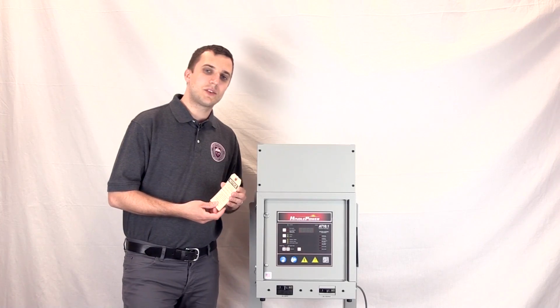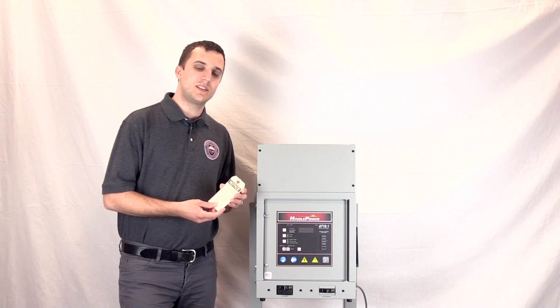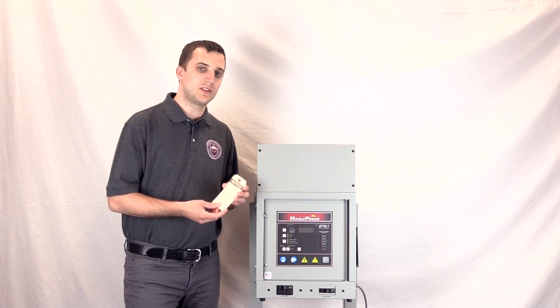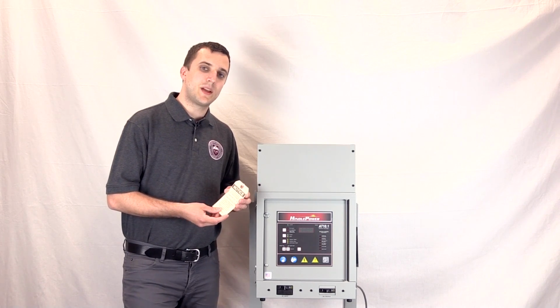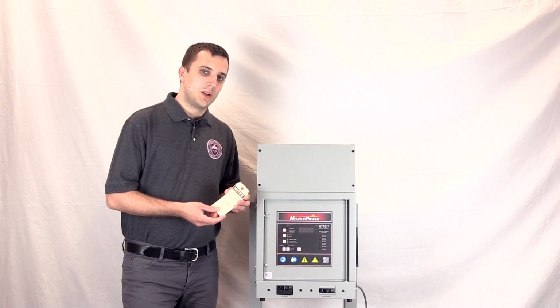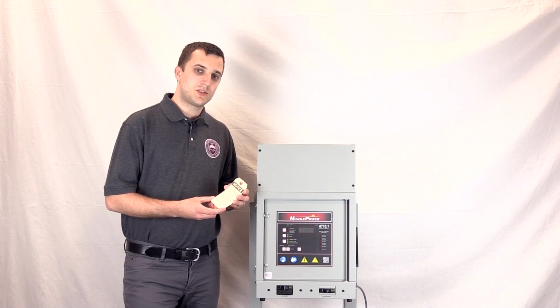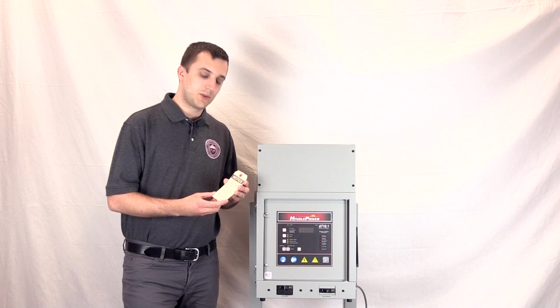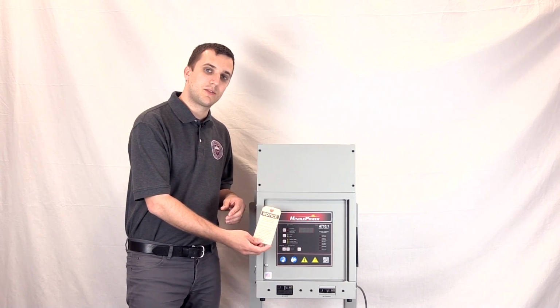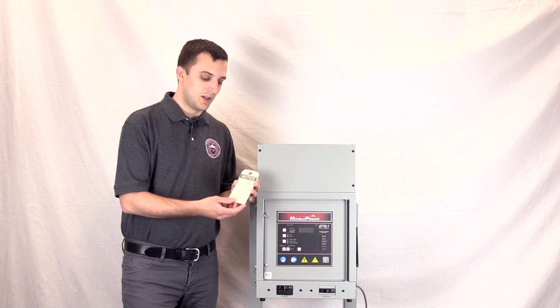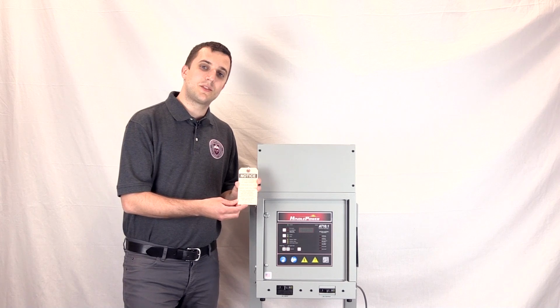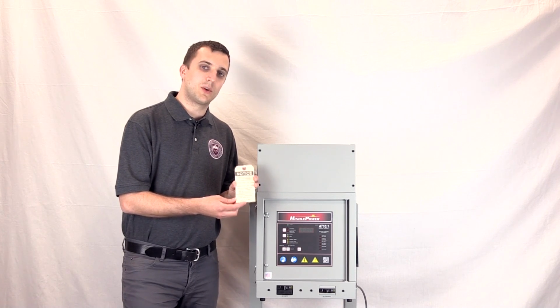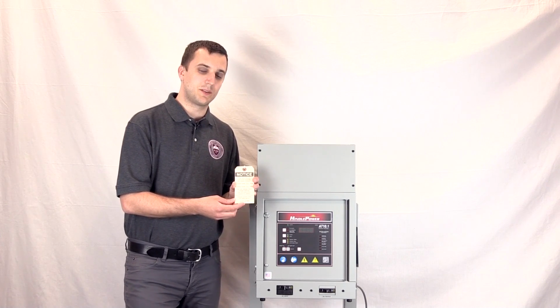Now that our AC power is connected, we want to continue on to the DC side. We want to connect our battery or DC bus to the I/O panel of the battery charger. We also want to verify this voltage with the charger's output voltage. So we want to check again on our tags on the front of the charger. We have a notice tag that has the float and equalized voltage for that battery charger and what it was tested at when it left our facility.